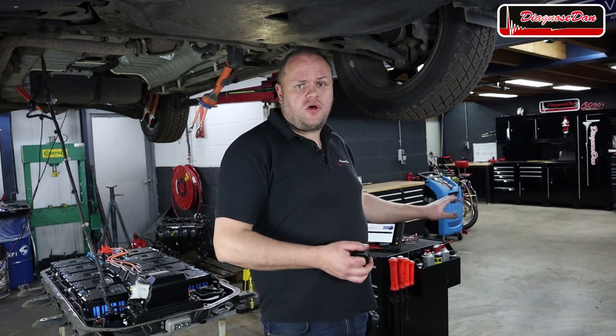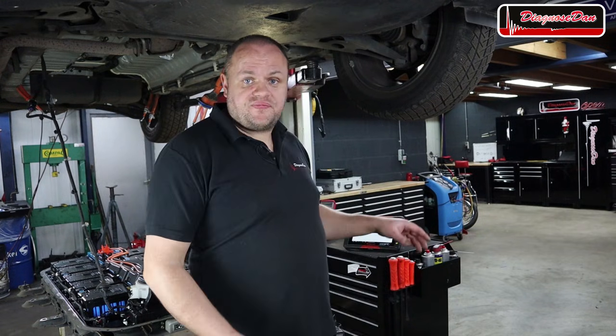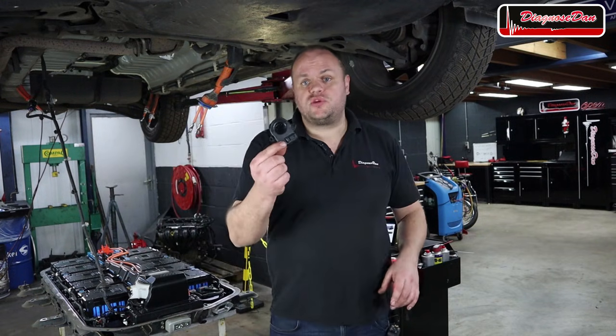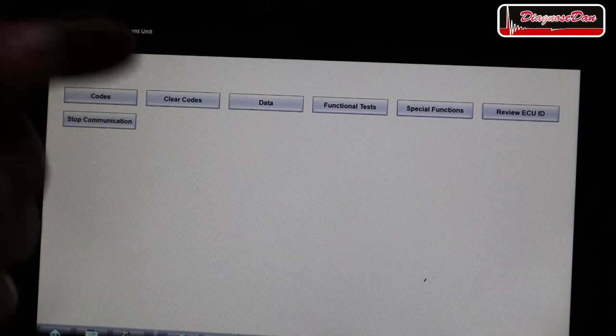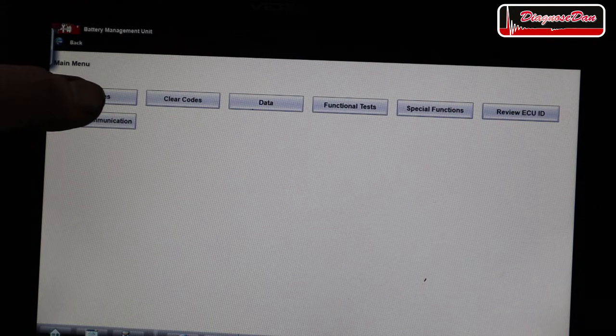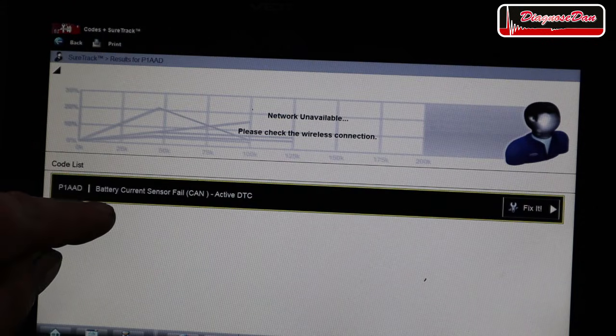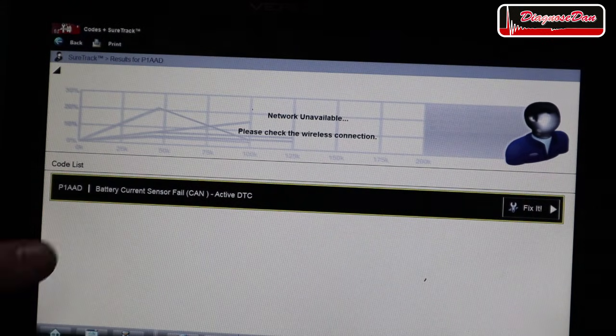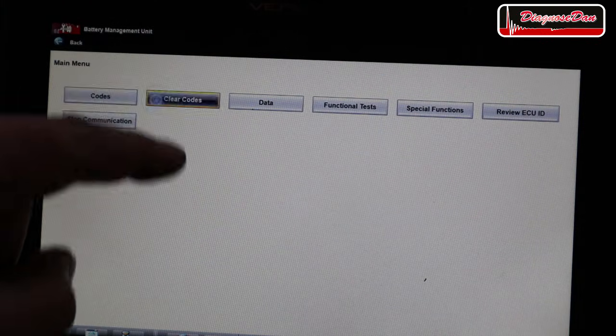So we're going to do a little test. We'll read the fault codes with the old sensor still installed and try to clear them. Then we'll hook up the new sensor, read and clear again, and see what happens. Right now we're inside the battery management unit. Let's read the codes—sure enough, we've got a fault code stored for the battery current sensor.